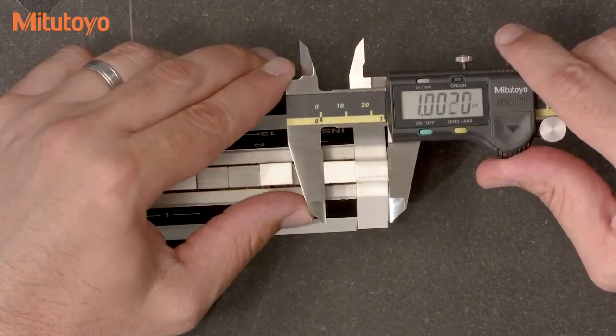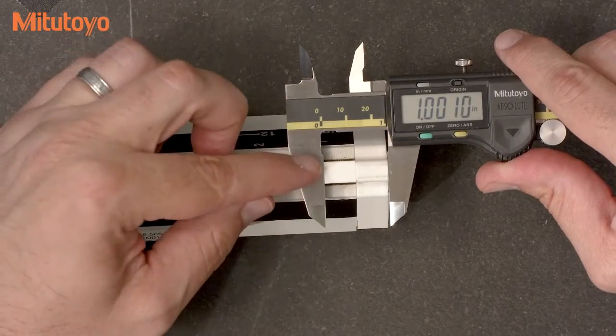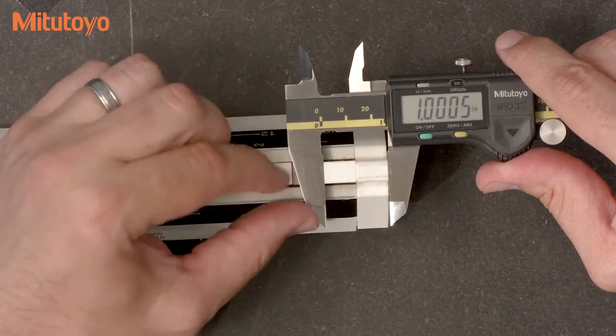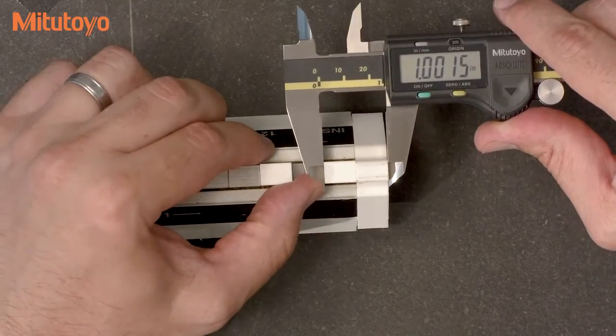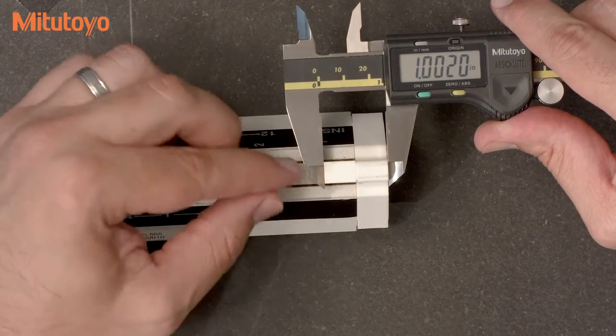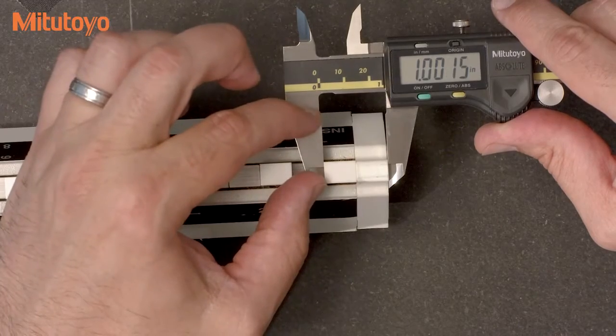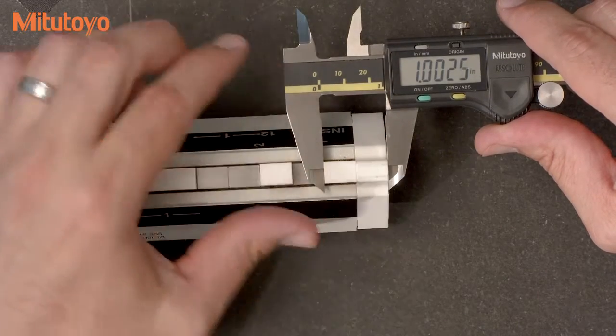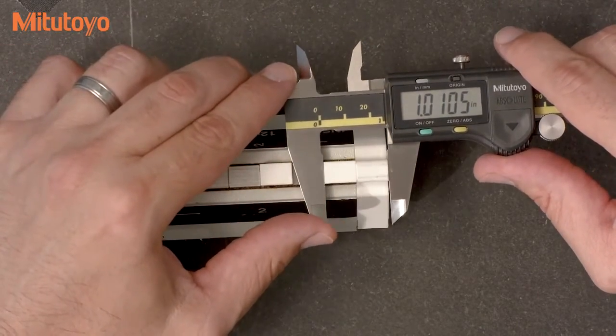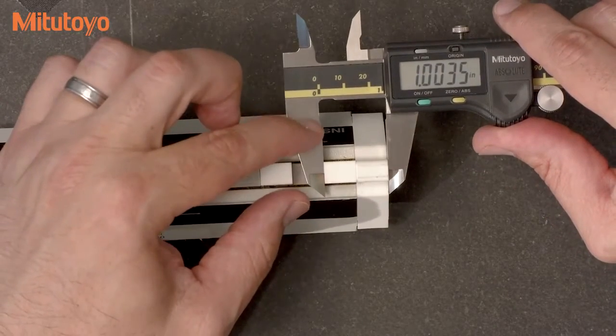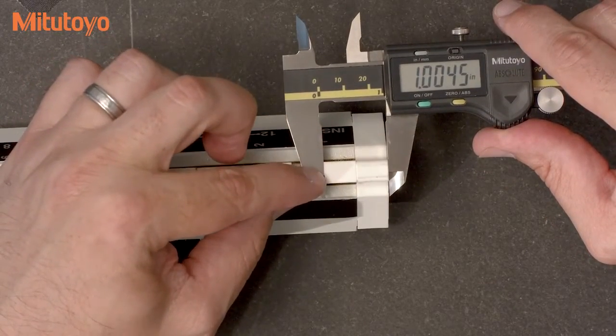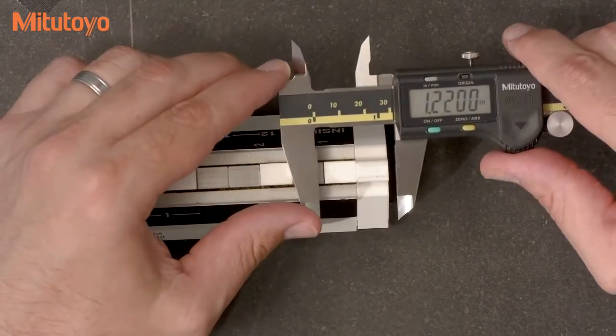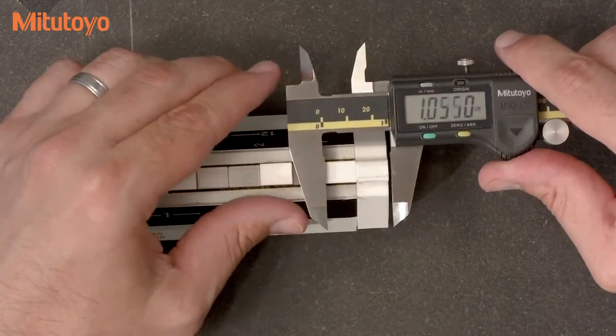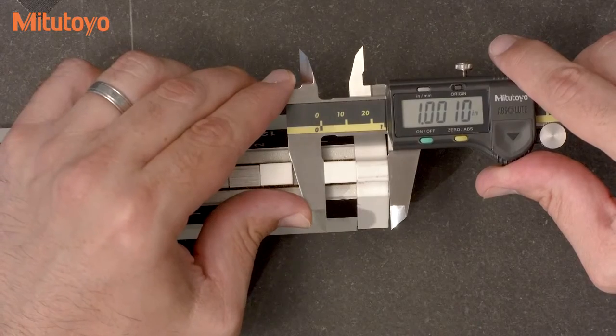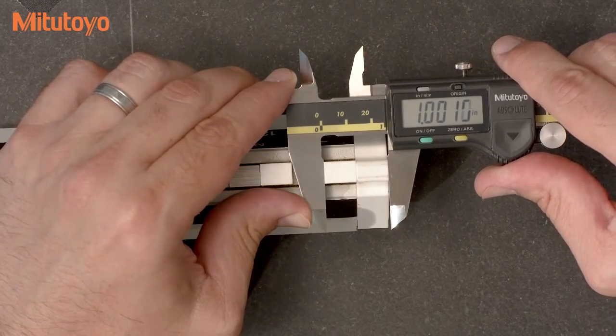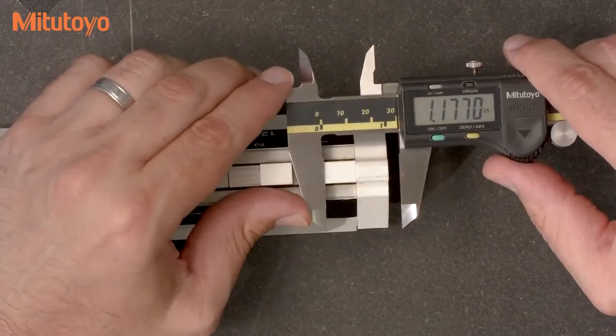In accordance to the ASME standard, the length specifications apply at any point across the measuring faces, thereby including any influence of the jaw parallelism. During the calibration, it's important to intentionally vary the distance from the beam at different test points. At the 1-inch point, I'll start close to the beam and report that value. I'll also check it further out just to see if the caliper may give me some problems.